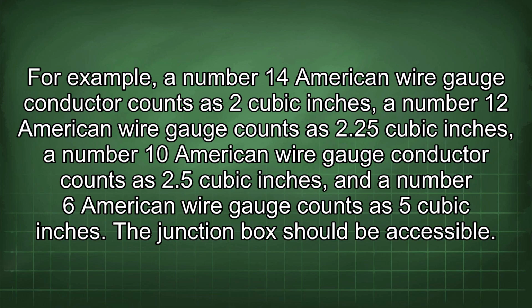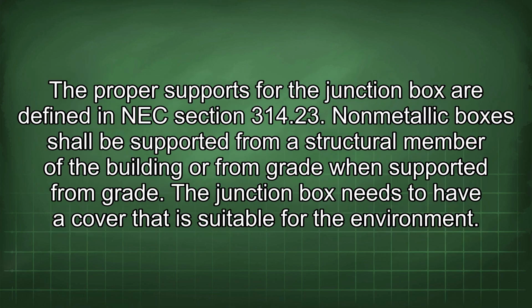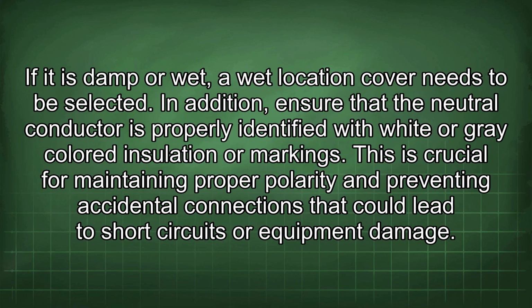The junction box should be accessible. The proper supports for the junction box are defined in NEC section 314.23. Non-metallic boxes shall be supported from a structural member of the building or from grade when supported from grade. The junction box needs to have a cover that is suitable for the environment. If it is damp or wet, a wet location cover needs to be selected.